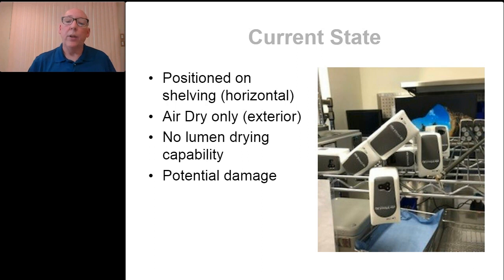And just allowing the devices to air dry, just kind of positioning them on shelving. Certainly the exterior will air dry these devices, but there's no lumen drying capability. And if you take a look by just placing some of these devices that we spoke about, very high profile devices, very expensive devices, just putting them on a shelf and letting them air dry, there's a potential for damage, isn't there? By potentially either placing too many upon themselves, or maybe one of them falls off, or another device is placed on them. So again, just allowing them to air dry is not going to do much relative to the lumen that's inside there.